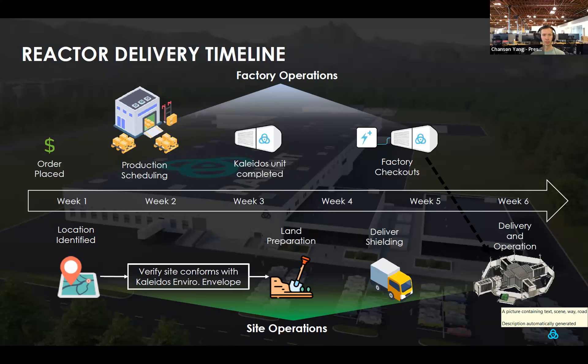The six-week deployment timeline works as follows: week one — order placed, production scheduled, Kaleidos unit identified; week three — Kaleidos unit complete; weeks four and five — factory checkouts, fuel loading, zero power criticality testing, and buttoning it up for transport. On the bottom are site operations occurring in parallel: location identified, verifying the site conforms with the Kaleidos environmental envelope, minimal land preparation — potentially pouring concrete, setting up a fence, delivering shielding — and then week six: delivery and operation.